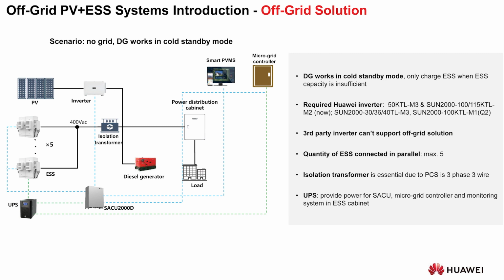Okay, everyone understand? So this scenario is with a DG generator. It's exactly the same as the previous one. The only difference is that you'll also have a diesel generator here. The diesel generator can work in cold standby mode, okay? Cold standby mode means that we can do on-off switching of the generator. When the batteries reach a certain level of state of charge, call it 10%, we can command the generator to switch on and charge the batteries up to a certain level again, maybe 40 or 50%, and then the generator switches off again. And when it reaches 10% again, it'll switch on again and charge the batteries again.